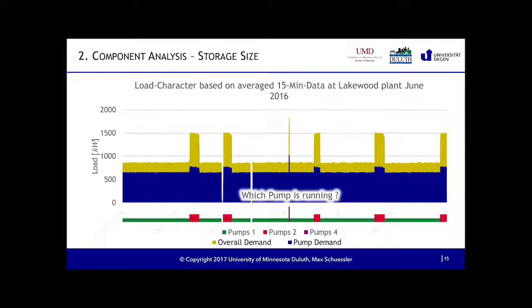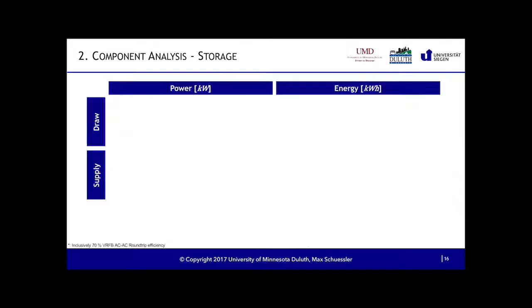So this bar right here, the green indicates if pump 1 was running, the red pump 2 was running, or the purple is when pump 4 is running. So you can see that our load is majorly influenced just by the pumps and how they operate. And how much of the total load they actually have compared to the treatment center, so the whole water processing, you can see by this difference right here. The blue is actually what the pumps use and draw from the system at 2,300 volts. And the yellow is the total Minnesota Power sees, so this difference is only what the treatment center actually uses. And the rest of the blue is what the pumps use for electricity. And then I looked for the battery.